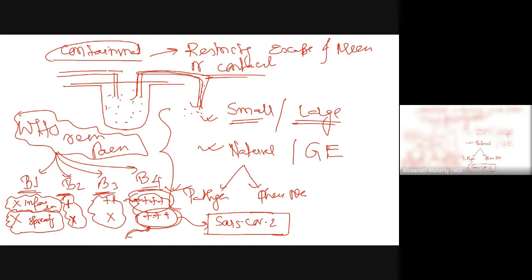Can I take out the exhaust steam in the room? No, I have to release even the exhaust through a vent, and it should be filtered. It should not be circulated in the lab itself. The whole air should be circulated out with filtration. So there is much rigidity in the protocol. There is much rigidity in the lab design or maybe the industry design which may be required when I am talking about the containment level.